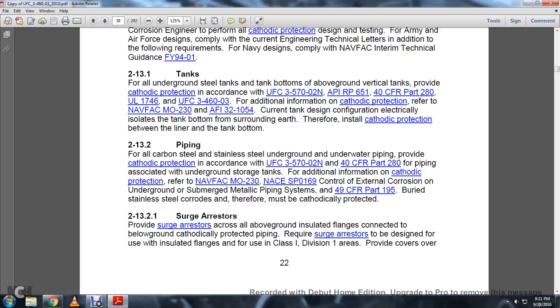2-13.2 Piping. For all carbon and stainless steel underground and underwater piping, provide cathodic protection in accordance with UFC 3-570-02N and Title 40 CFR Part 280 for the piping associated with the underground storage tank. For additional information on cathodic protection, refer to NAVFAC MO 230 and NACE SP0169, control of external corrosion on underground or submerged metallic piping systems, and Title 49 CFR Part 195. Buried stainless steel corrodes and therefore must have cathodic protection.